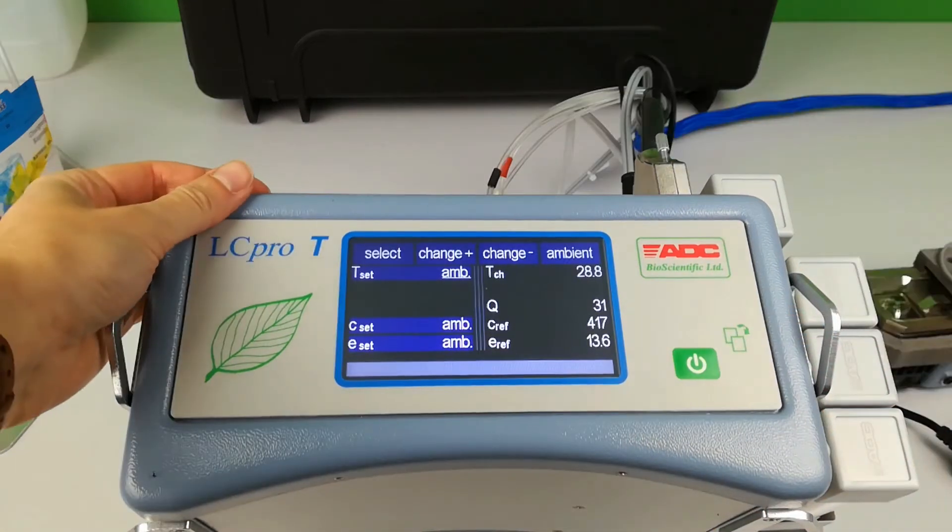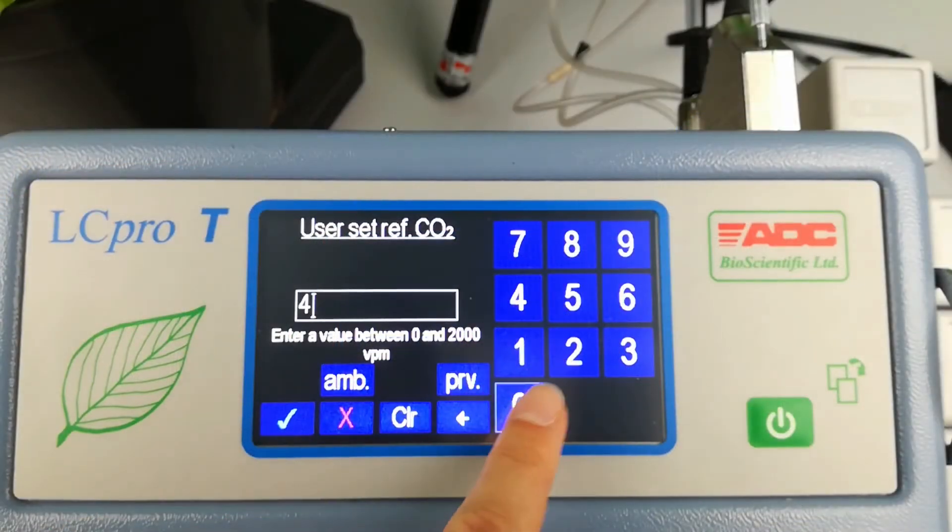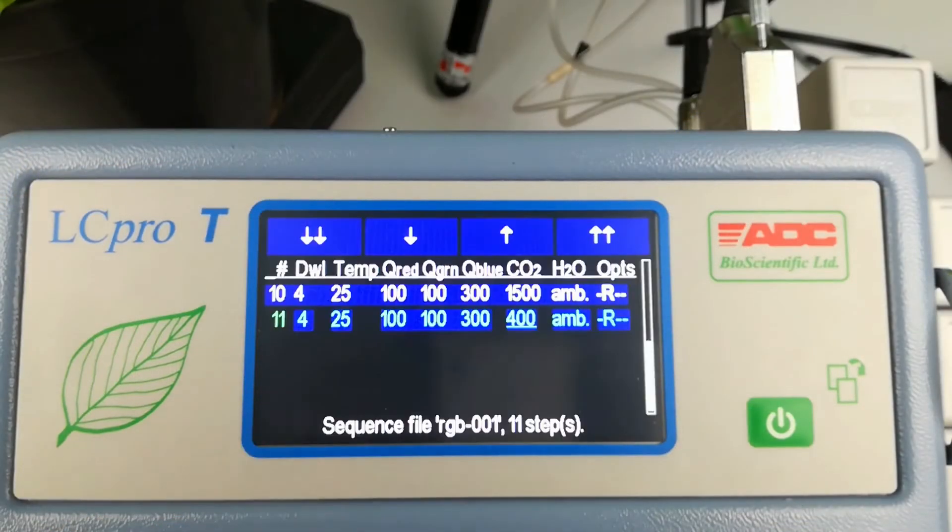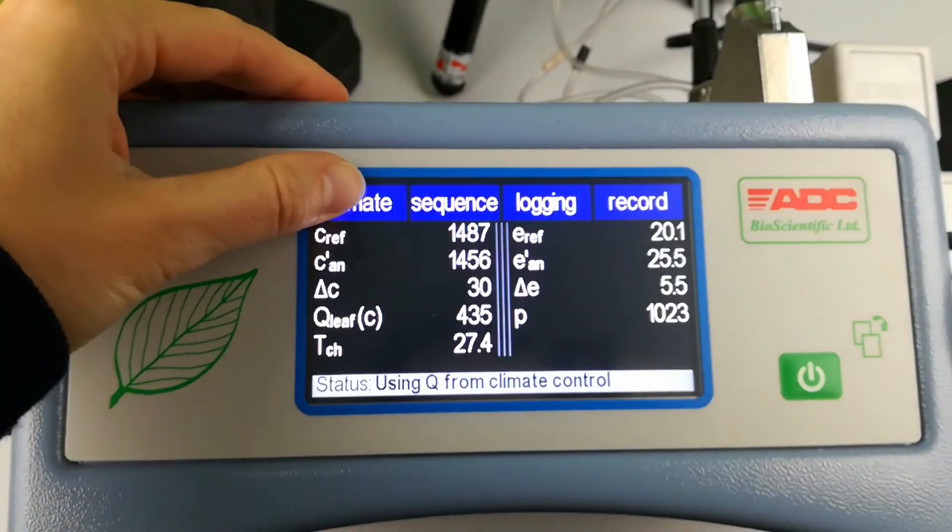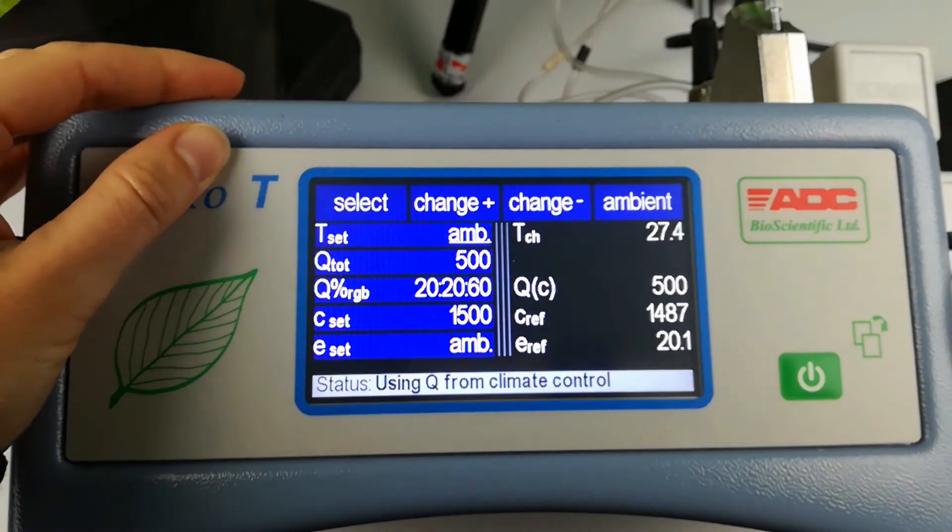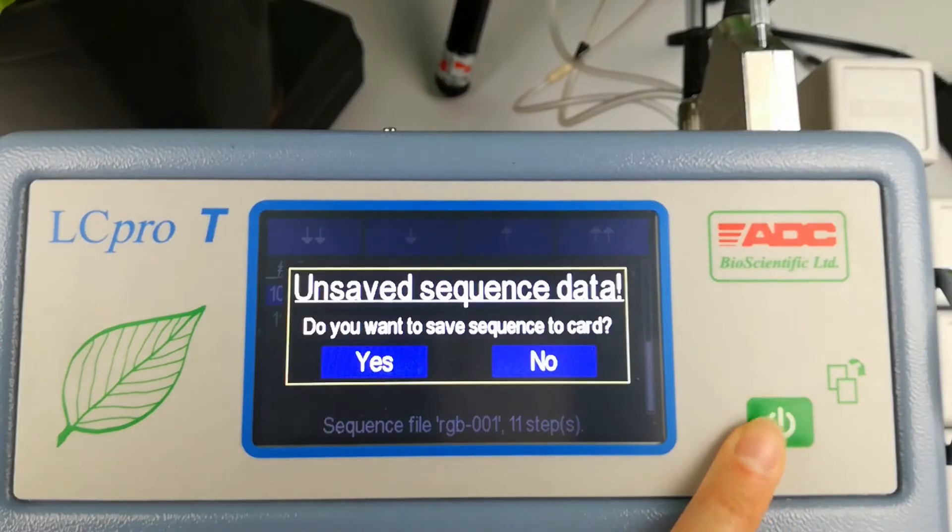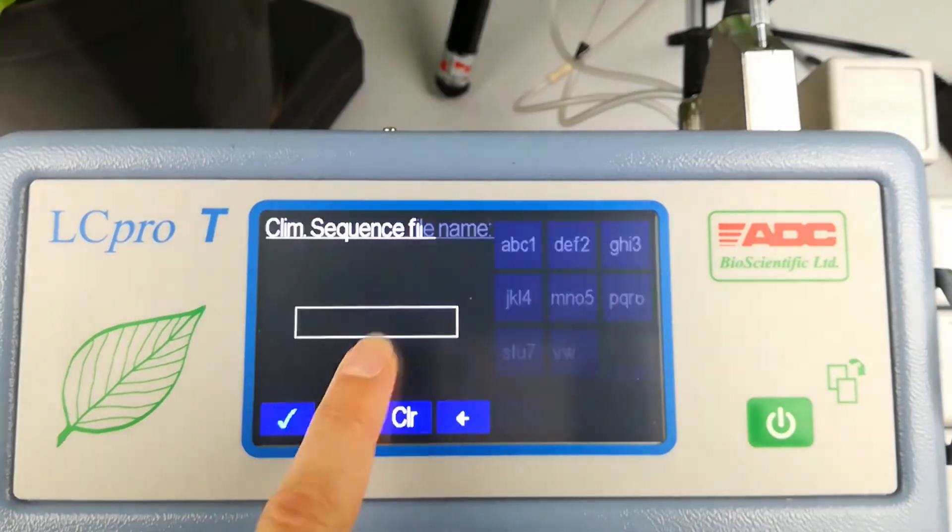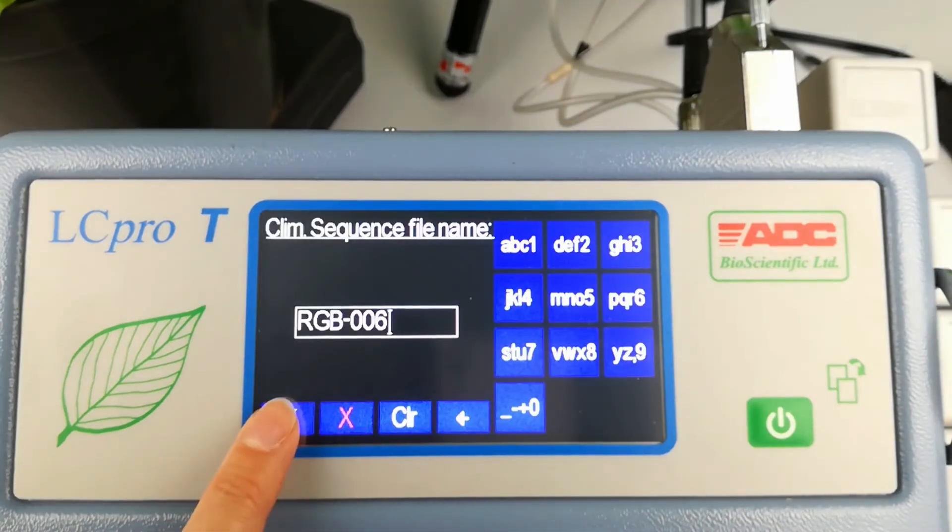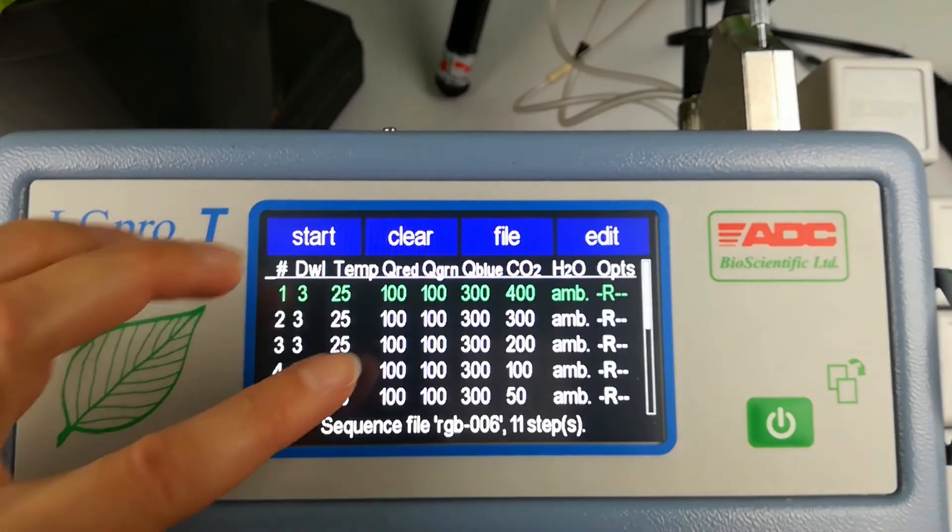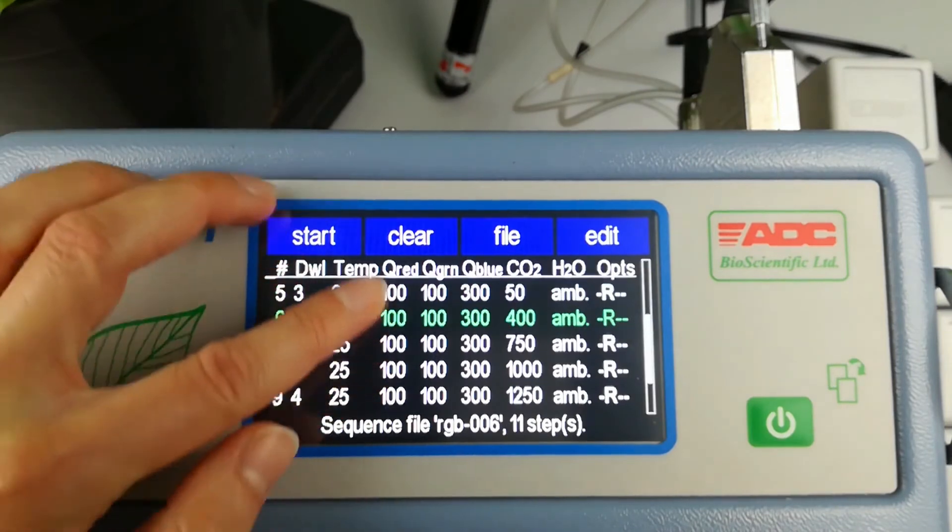The LC-PRO-T can be programmed to automatically control the leaf chamber climate. CO2, H2O, light and temperature can all be controlled at constant or sequential levels, either individually or in any combination.